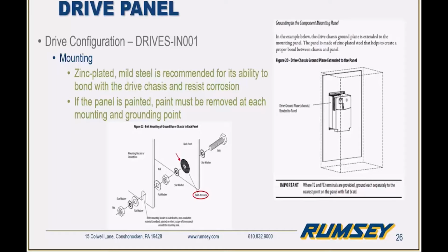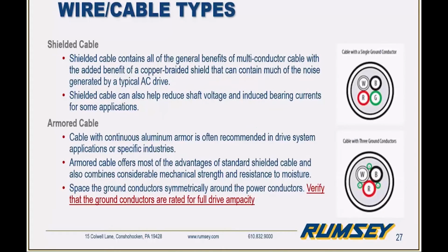Yeah, thank you, Sean. So moving on to cable types, there's really only two cable types that should be considered when using a VFD. A shielded cable does a good job of containing the common mode noise, and also helps to prolong the life of the motor. In situations where you may need some more mechanical strength or resistance to moisture, you may want to consider using an armored cable.